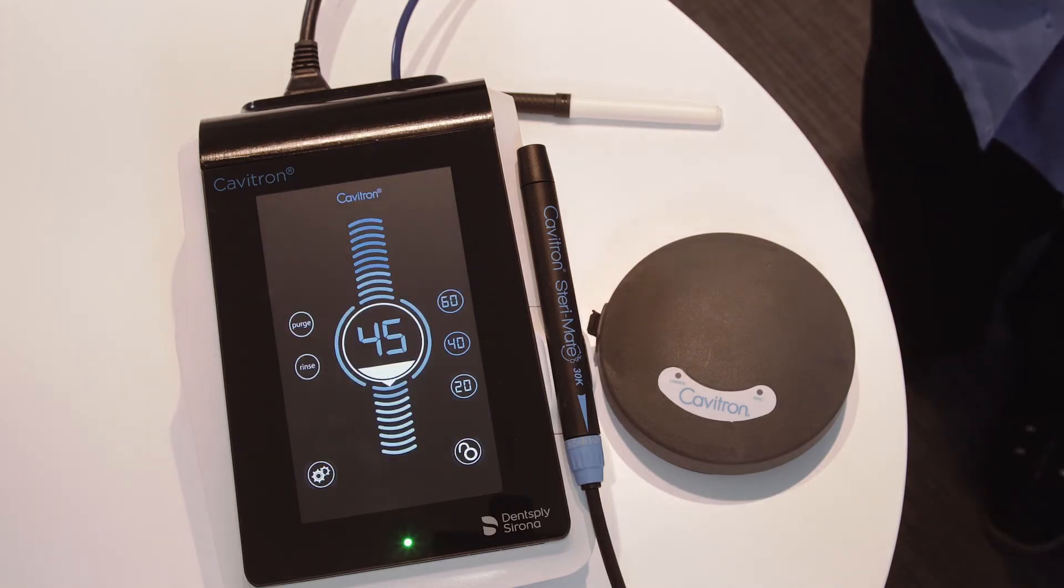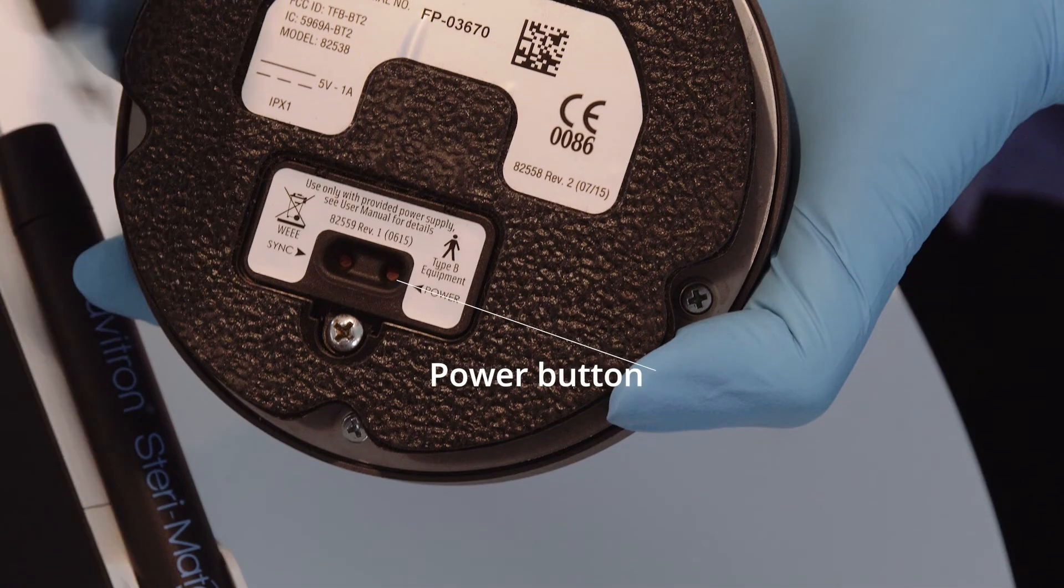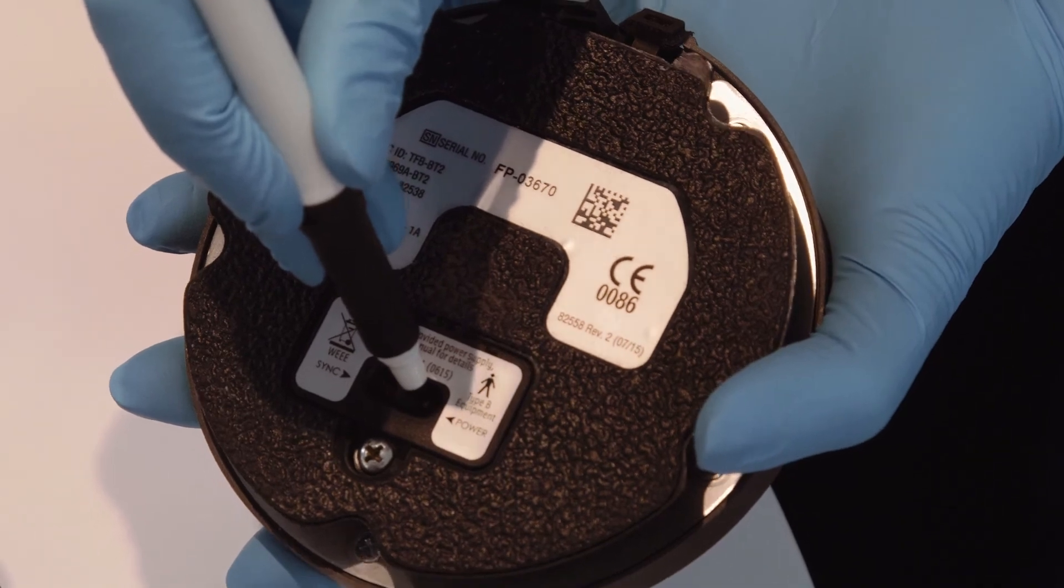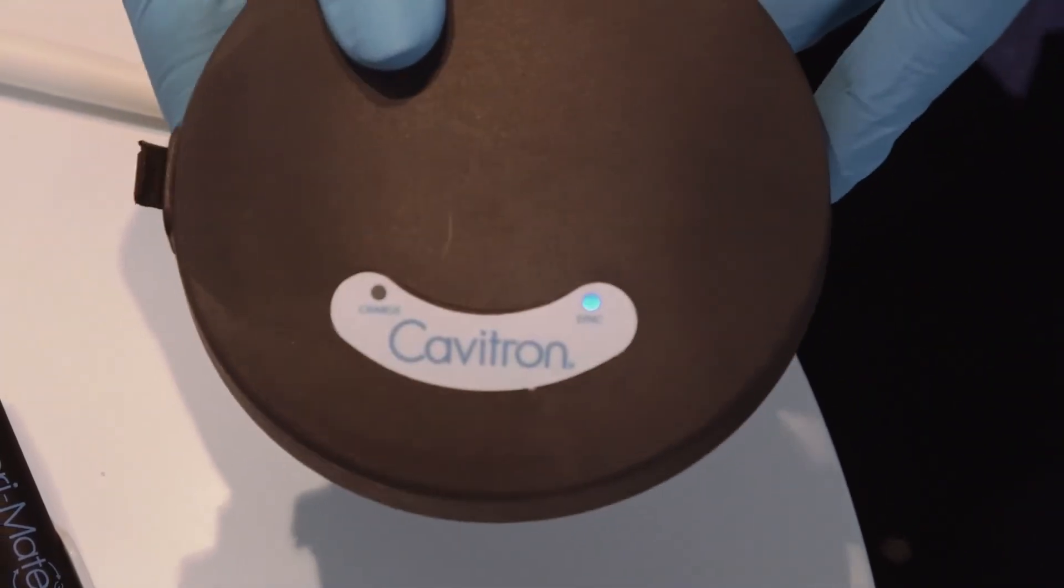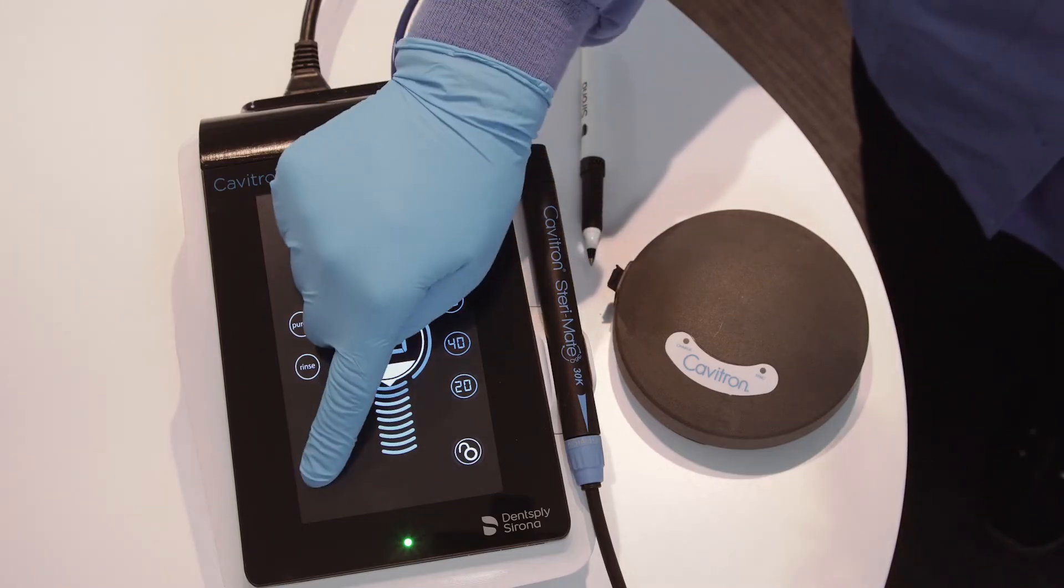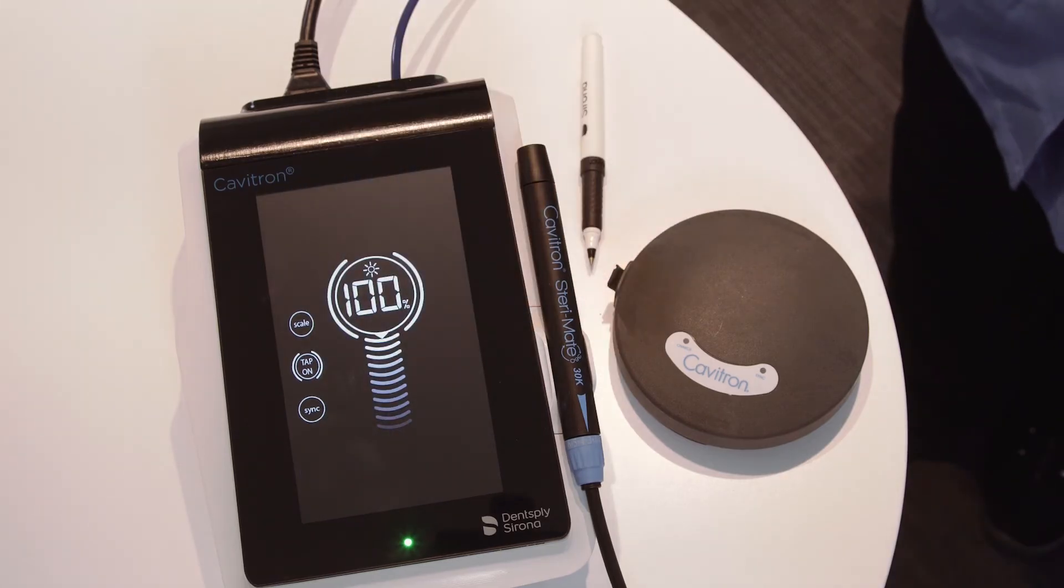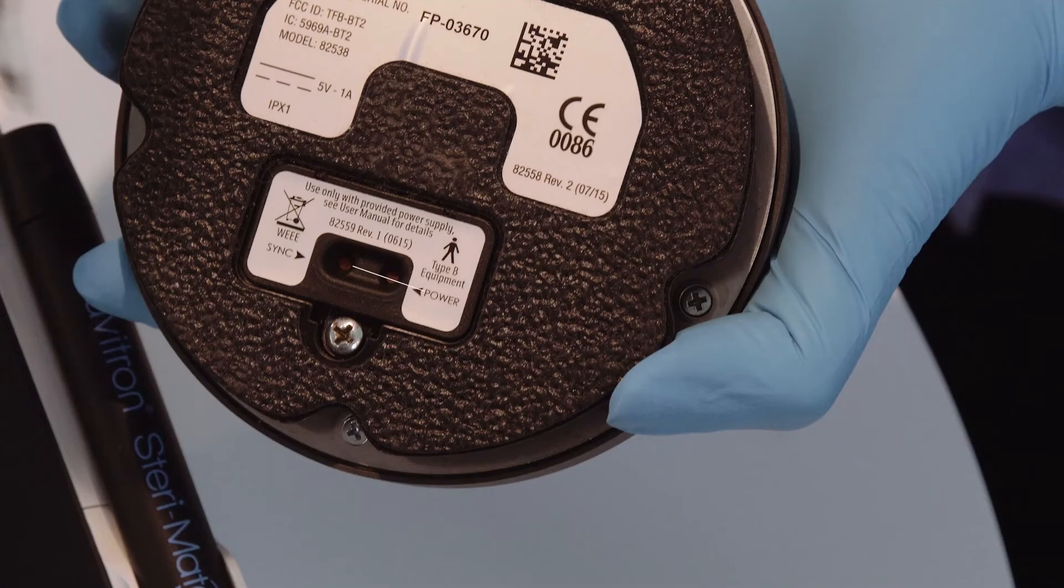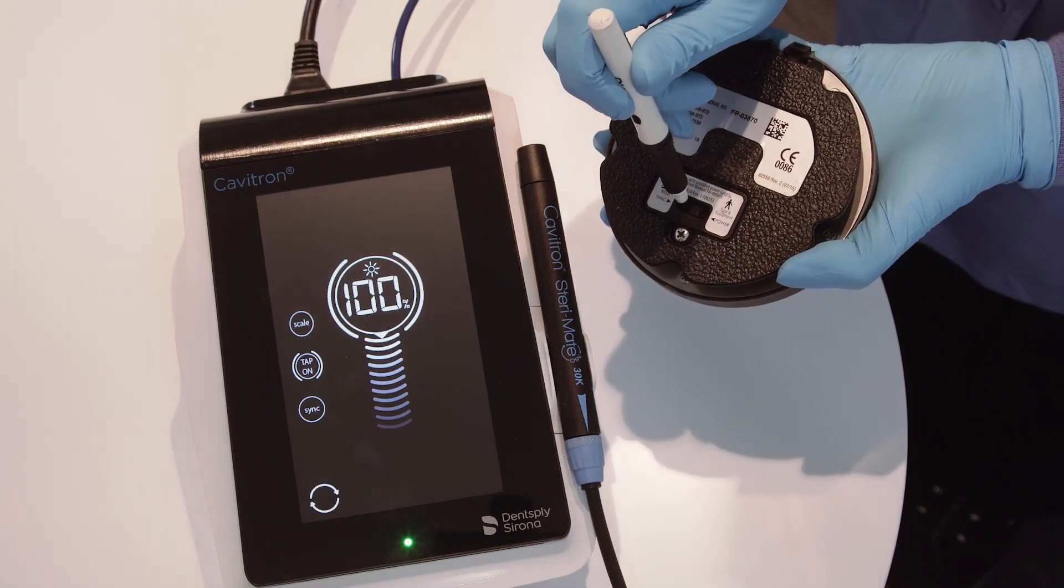Next, turn on the foot pedal by pressing the power button on the bottom of the foot pedal and hold for at least three seconds. A light on the top of the foot pedal will illuminate to verify power. Next, press and hold the settings icon until the settings screen appears. Tap the sync icon on the settings screen, followed by pressing the red sync button on the bottom of the foot pedal and hold for at least three seconds.